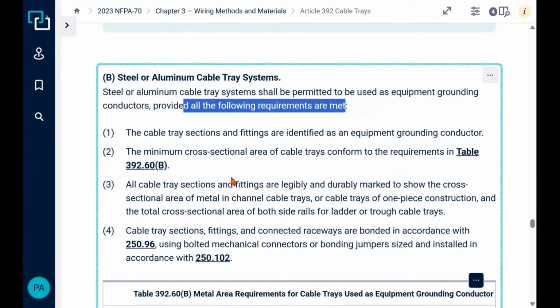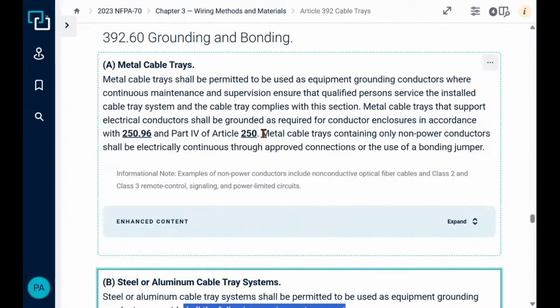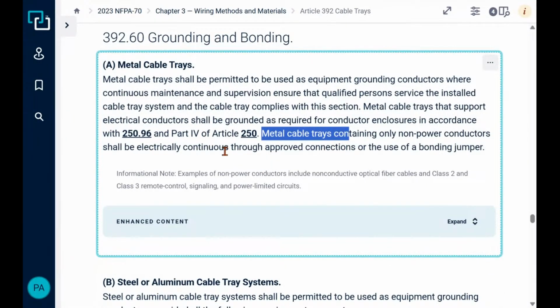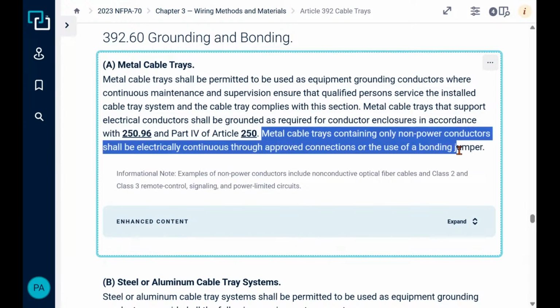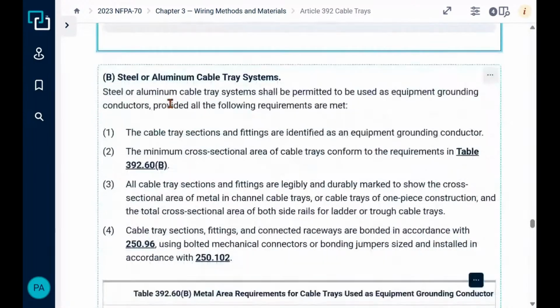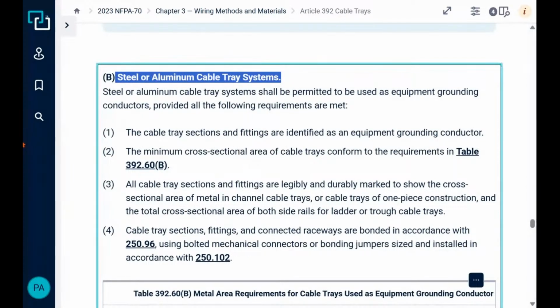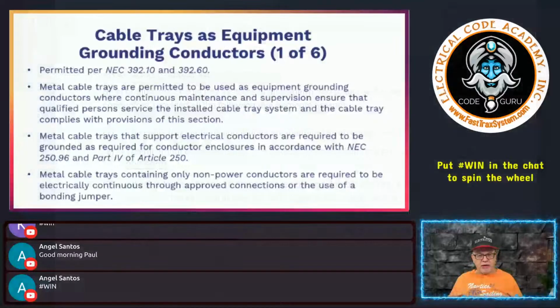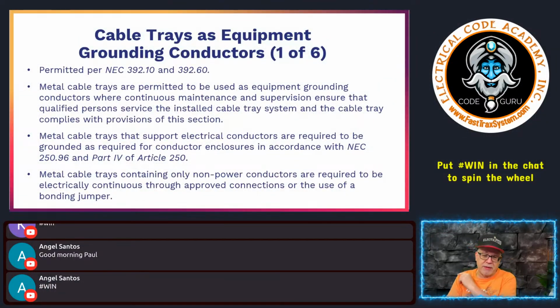Up here it's just telling you right off the bat: if you're using a metal tray for non-power stuff, like the fire alarms, fiber optics, it will be continuous. And if it's segmented and not continuous, then it'll have bonding jumpers that make it act like it's electrically continuous. That's just a general statement for all those non-power things. Then you get down into these, and this is where you're going to have to meet all these requirements if you're going to be using a normal metal cable tray. So I wanted to make sure we differentiate it. But that's a good example of an informational note. I'm a big fan of informational notes, only because I think that if we use them right, they can give direction to the code user. Not instructions, but extra directions to where to go, where to look, and things like that. I'm a big believer in that.